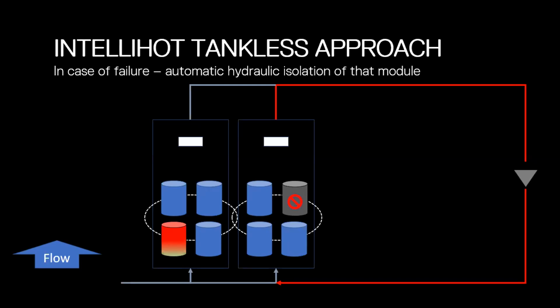And that's a big key here. The single point of failure, which really you don't have. The only thing that could take a whole cabinet offline would be a power failure, or all of a sudden you lose gas to the building, or something like that. So there's very little. The only thing that's common in the cabinet itself is the display, which is that little white box right in the upper middle part of each one of those units. You can actually cut the display off of there and it will still fire and still run at the same settings as before. So like I said, inside the cabinet, there really isn't much that's going to cause the entire unit to go down. So that single point of failure is basically non-existent.